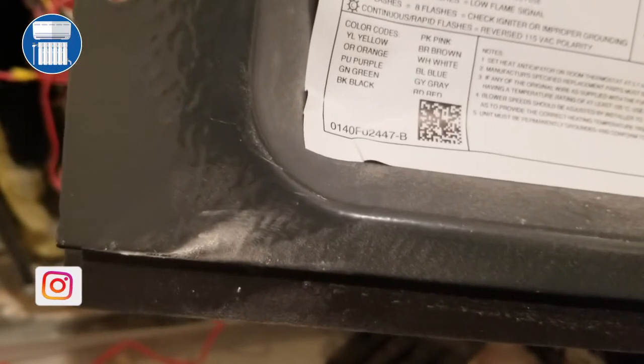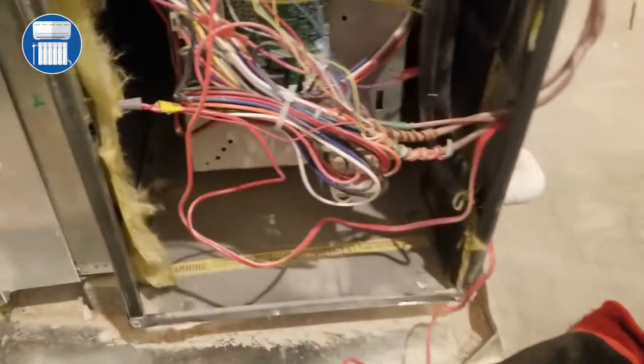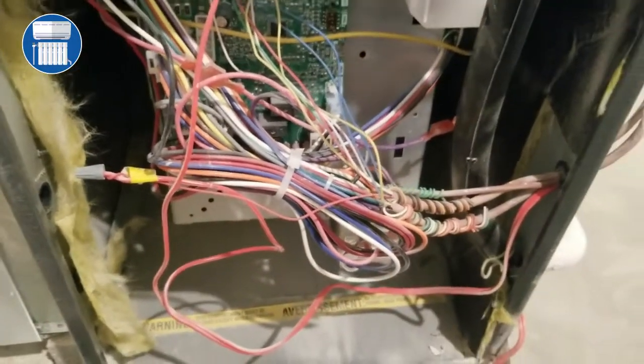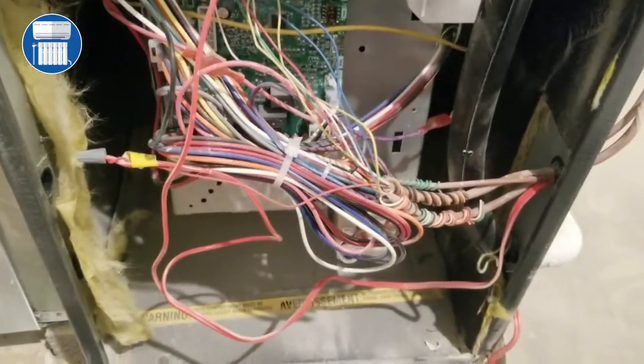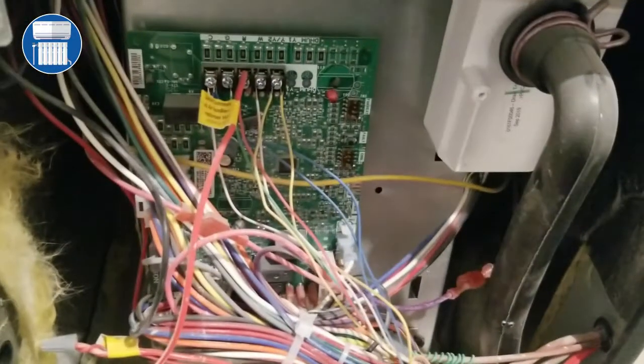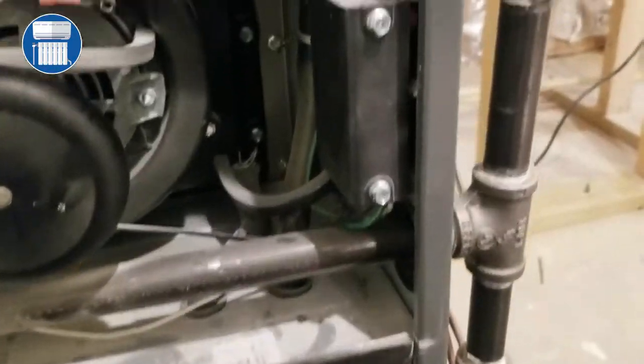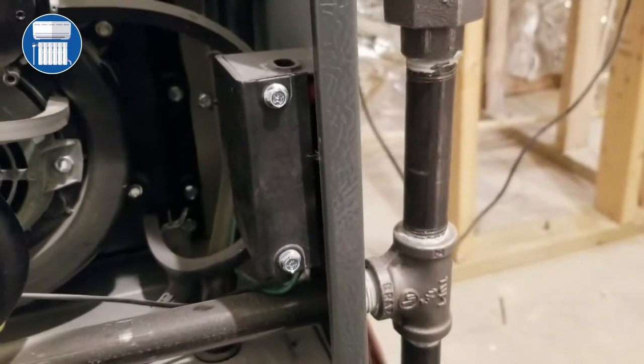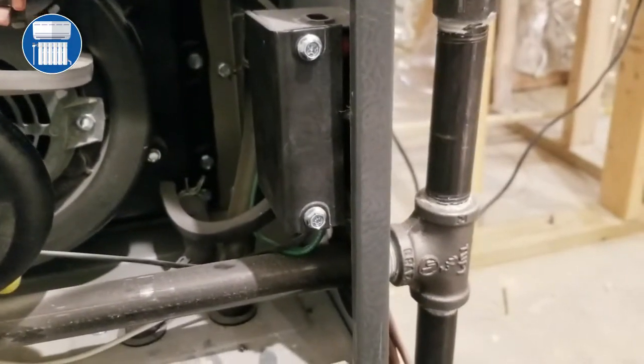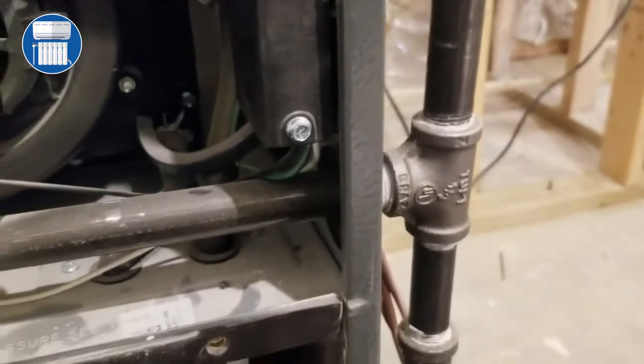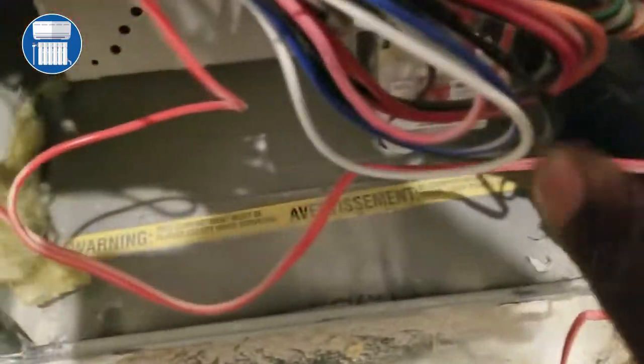If it's off, it says it's a control failure. That means you're not getting any power at all. If that light is not coming on at all, you may want to check your high voltage to see if you have 120 going in there. That's the first thing you want to check. The next thing you may want to check is the transformer here that breaks the 120 down to 24 volts throughout your furnace. But this is not exactly what I want to concentrate on today.